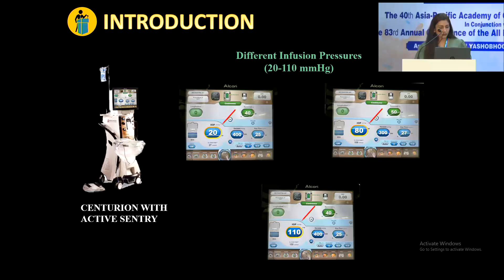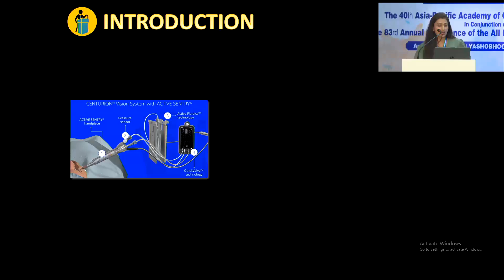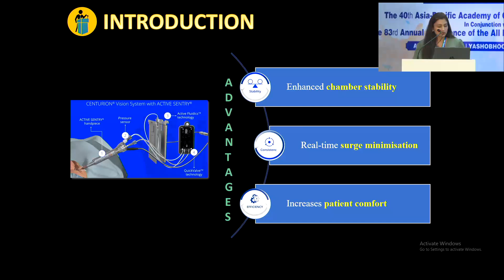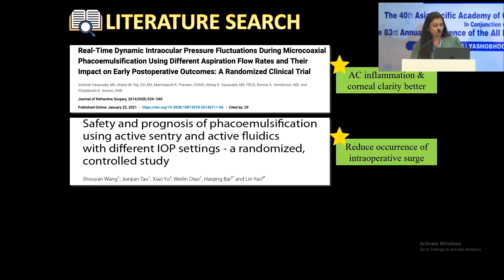So using the Centurion machine with active fluidics, we can operate at various infusion pressures ranging from 20 to 110 millimeters of mercury. What are the advantages of operating at a low IOP setting? Basically, operating at low infusion pressure mimics the physiological IOP of the eye and hence increases patient comfort. It also enhances chamber stability and minimizes surge. There is abundant published literature on the benefits of operating at low infusion pressure.